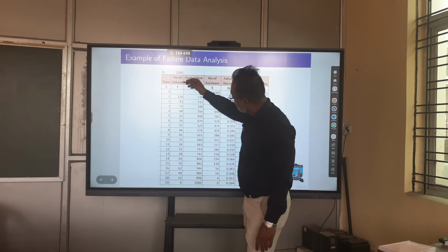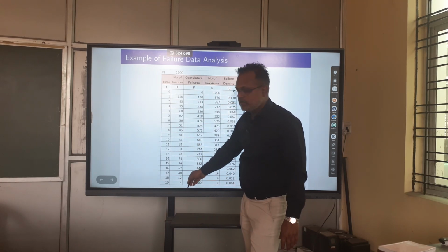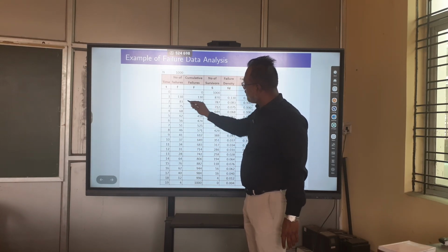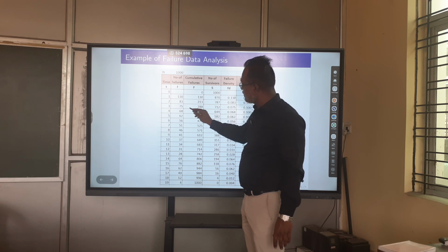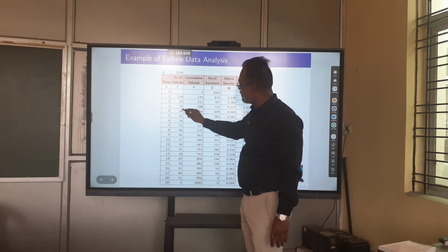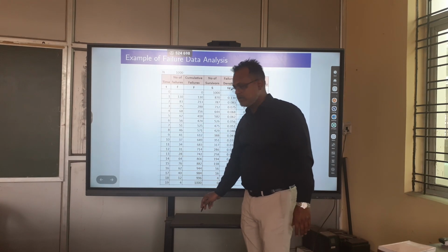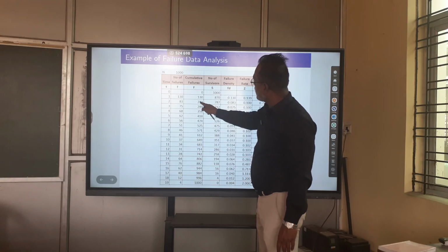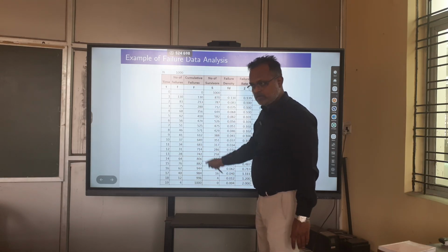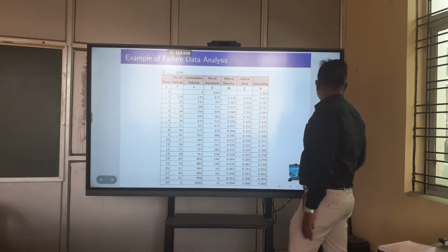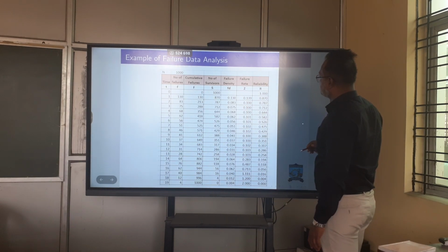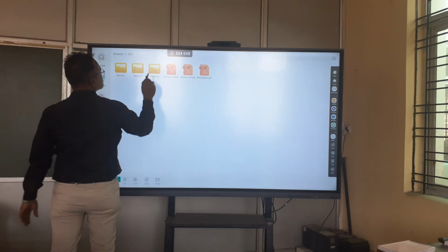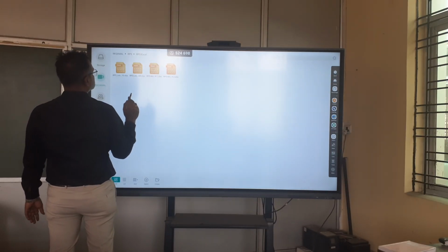Every hour so many failures occur. And what are the cumulative failures? For example, first hour 130, second hour 130 plus 83, third hour 130 plus 83 plus 75, fourth hour 130, 83, 75, 68, and so on. The number of survivors is simply 1000 minus 130, 870 minus 83, 787 minus 75, and so on. These are the number of survivors. Let me check if I have given you the Excel sheet or not. Yes.